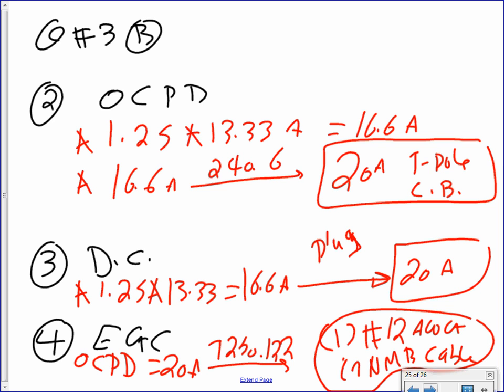Done. So that's how you size, guys, for garbage disposal, dishwasher, fans, and water heaters. I hope that was a review from what we did yesterday. The more we do them, the more it emphasizes in your mind, guys, that every time you have a load, you have to ask yourself: I need to size the overcurrent protection device, the branch circuit, the disconnect, the overload, the equipment ground conductor. What I didn't size here is the conduit, but you guys went through the conduit. You can easily size the conduits, but we're not using conduits anyway. We're using NM cable. But if it wasn't an NM cable, then you have to size the conduit.